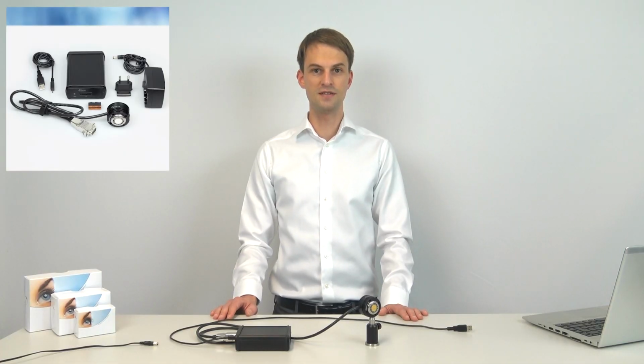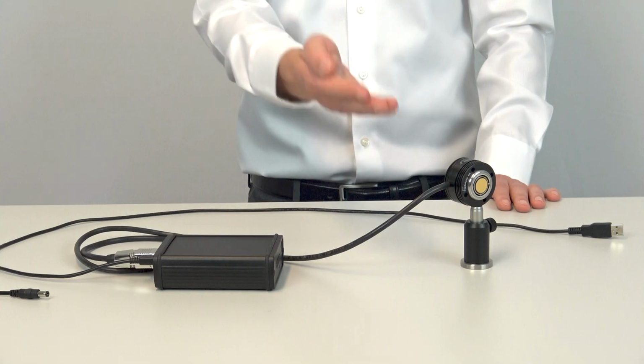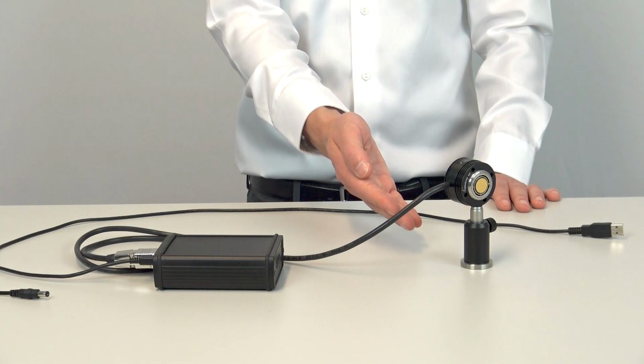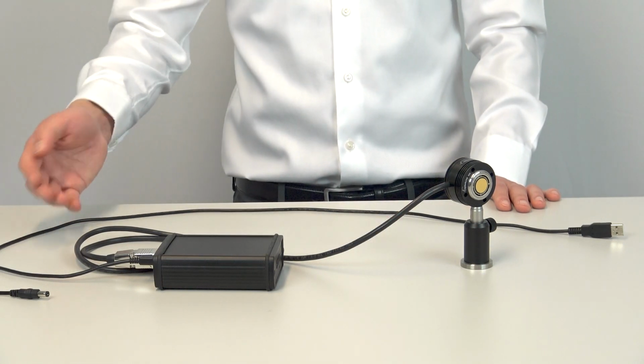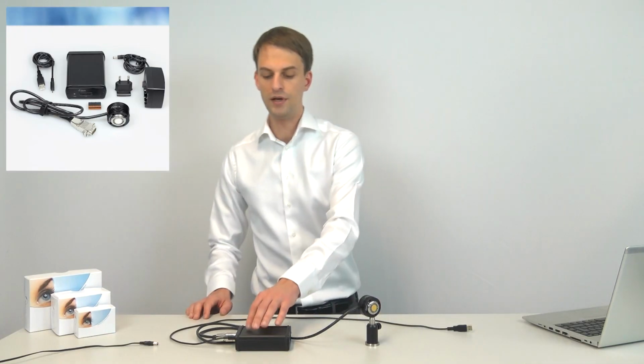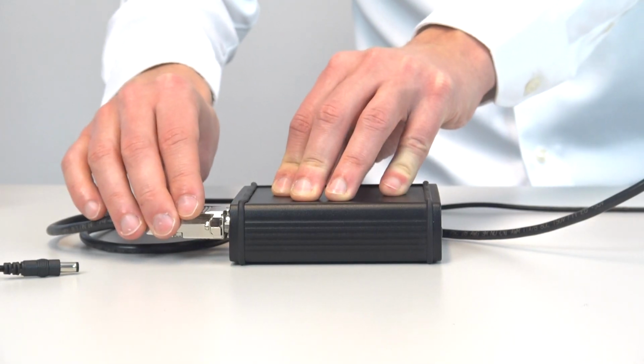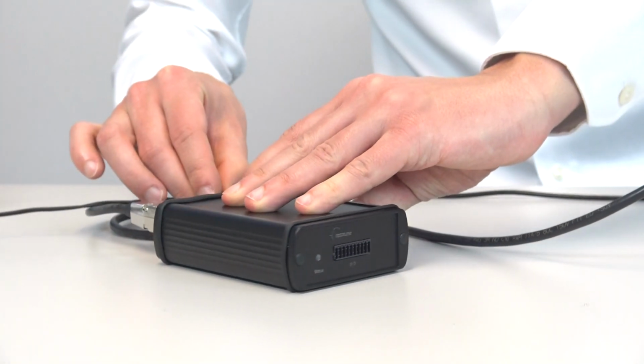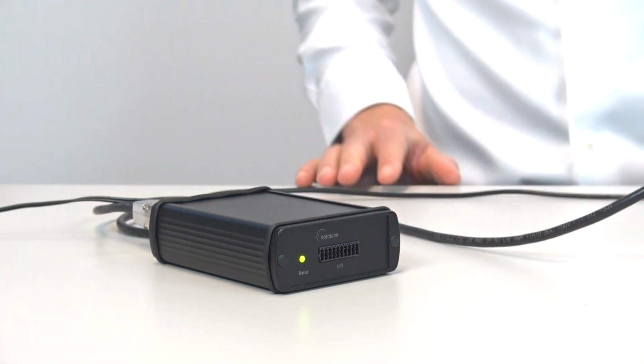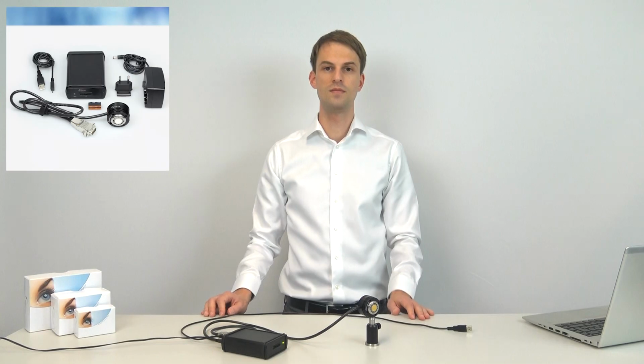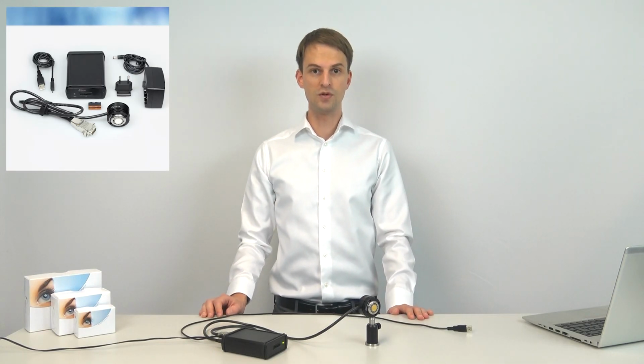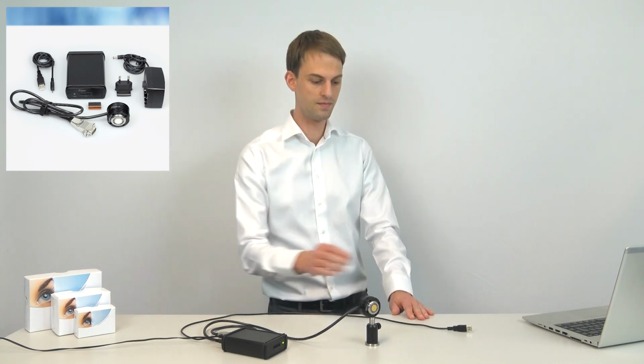So, as you can see, I have now mounted the mirror head onto an optical post and connected it to the base unit. Please make sure to properly connect and secure the cable before powering up the device. Next, I'm going to show you how to use Optotune Cockpit to control our mirror.